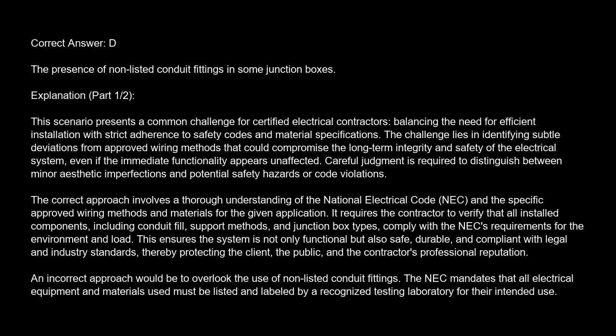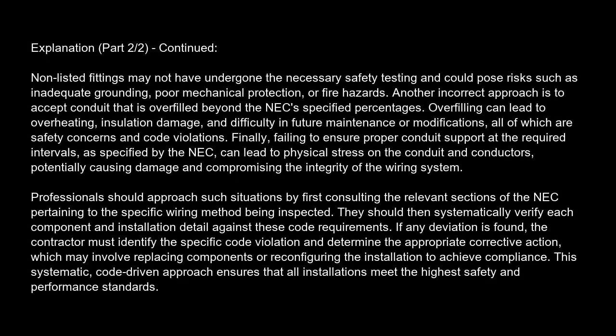An incorrect approach would be to overlook the use of non-listed conduit fittings. The NEC mandates that all electrical equipment and materials used must be listed and labeled by a recognized testing laboratory for their intended use. Non-listed fittings may not have undergone the necessary safety testing and could pose risks such as inadequate grounding, poor mechanical protection, or fire hazards.